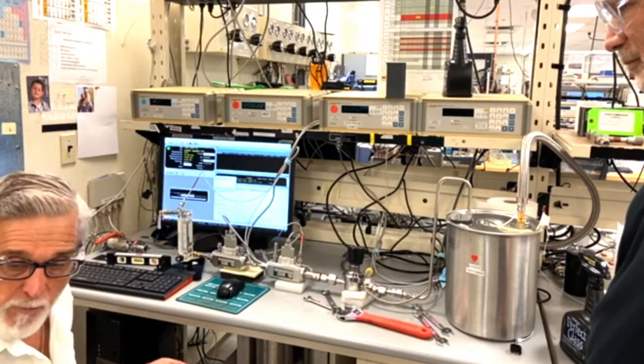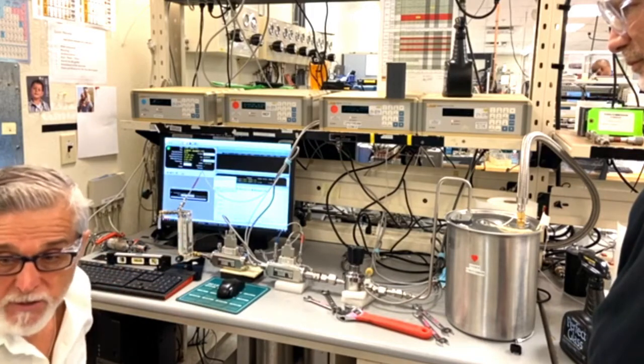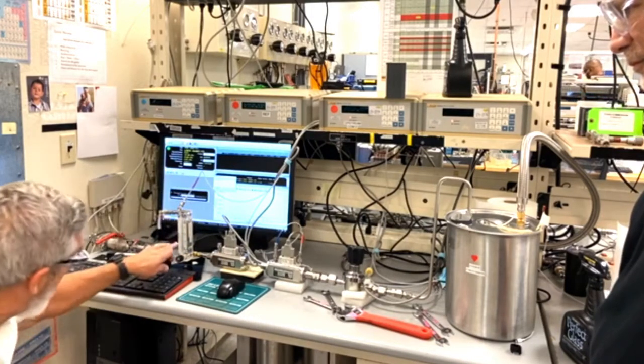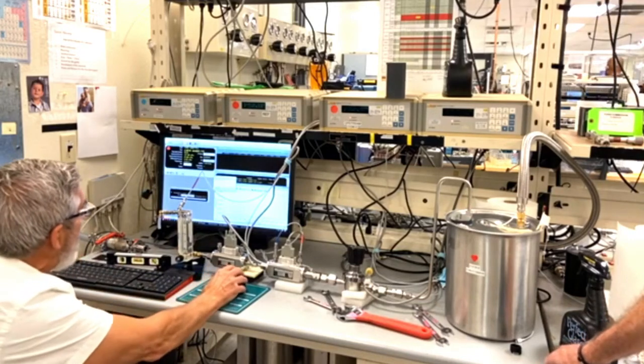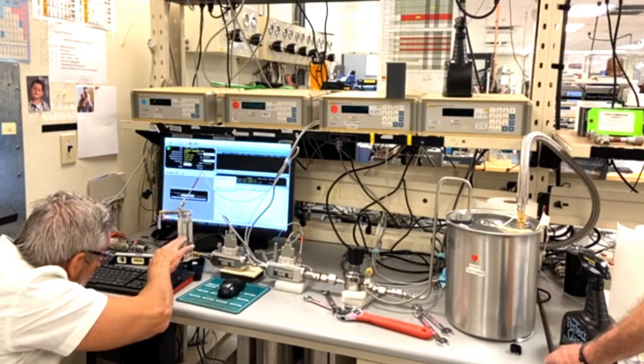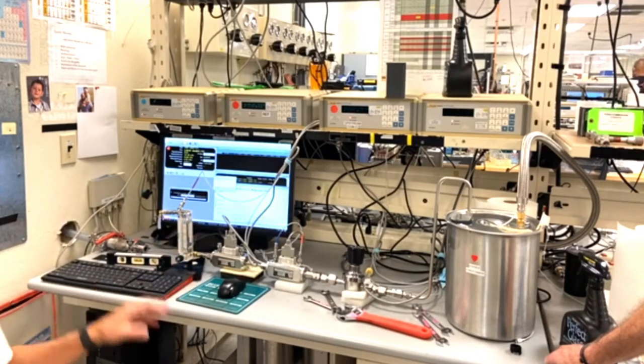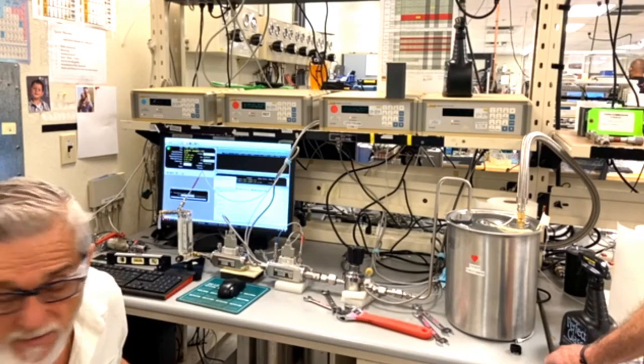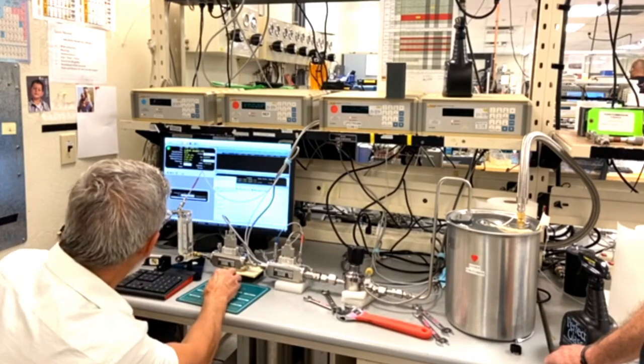Many of the rotameters, you have to measure the ball where the manufacturer states, which is typically in the center of the flow. And once we get it all set up on the proper number here, we make sure the flow is stable. And then we take a reading by hitting the start button.